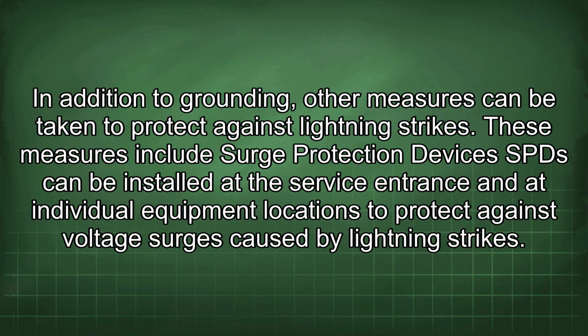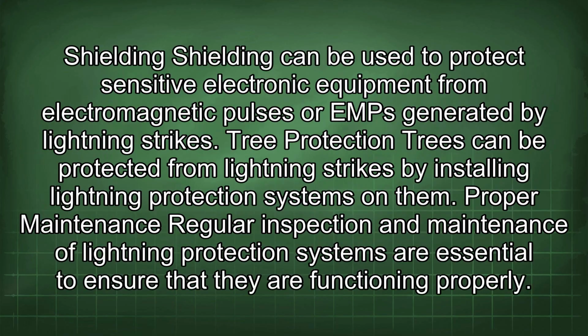In addition to grounding, other measures can be taken to protect against lightning strikes. These measures include surge protection devices. SPDs can be installed at the service entrance and at individual equipment locations to protect against voltage surges caused by lightning strikes. Shielding can be used to protect sensitive electronic equipment from electromagnetic pulses, or EMP, generated by lightning strikes.